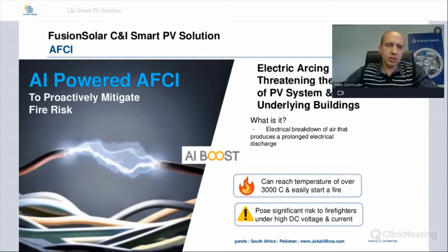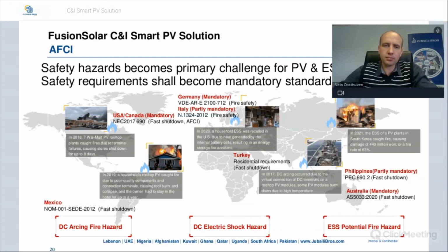So AFCI. What is AFCI? AFCI is arc fault circuit interruption, and Huawei has an AI-powered version, which means artificial intelligence. Electric arcing is threatening the safety of PV systems and underlying buildings. An electric arc can happen from a simple misconnection where an MC4 connector is not 100% connected. As we all know, DC power is more dangerous than AC with the high voltages, so it's very difficult to extinguish a DC arc compared to an AC arc. But Huawei has artificial intelligence on its side. It will learn from previous occurrences of AFCI. So if it picks up an arc, it will switch off. And if it was a false trigger of the AFCI, it will learn from that, and next time it will know that it was false.